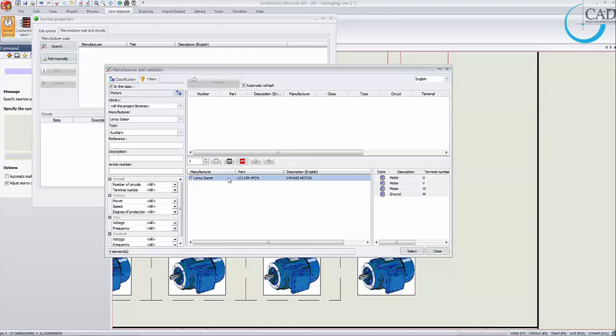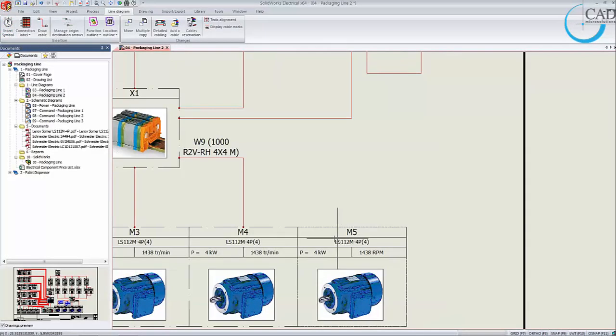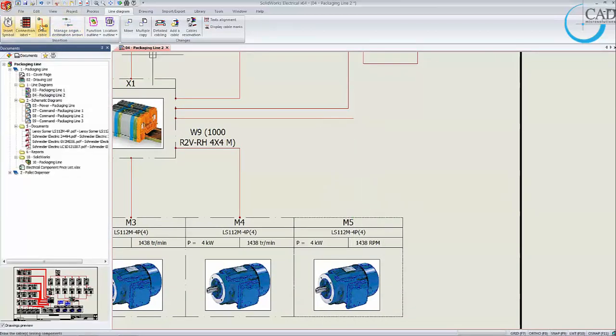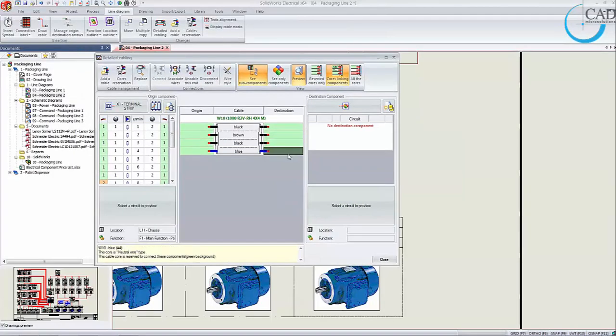Adding manufacturer parts brings in the four circuits involved with this specific component — three motor circuits and one ground circuit. The states of the circuits are still blue because we have not yet gone into the actual wiring of the cores. We will do that later in the multi-wire drawing. Now that we have placed the motor line diagram symbol, we will go ahead and draw a cable between them. We can also associate this cable to a previously defined cable whose cores have not yet been defined.